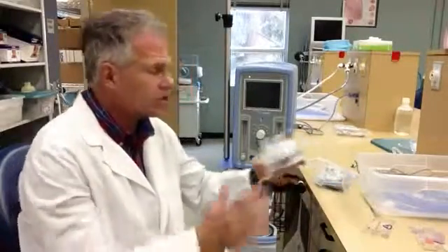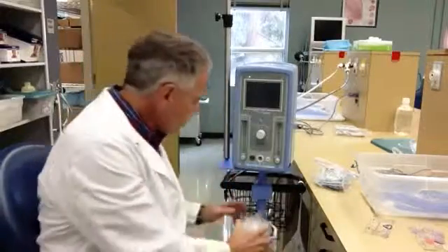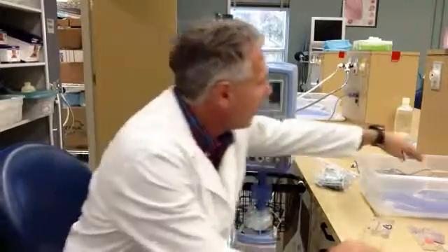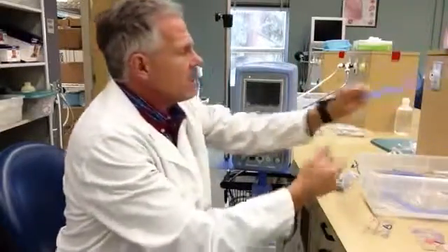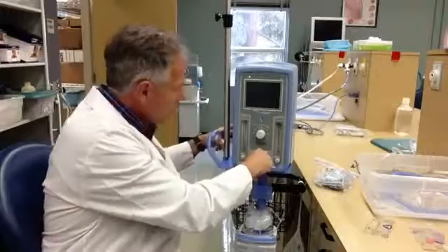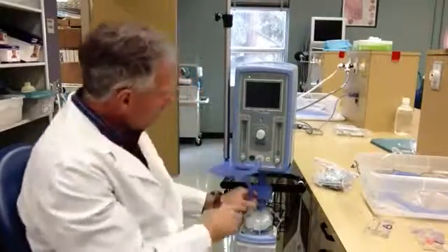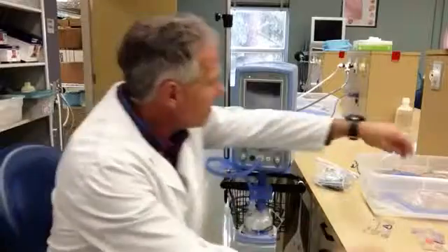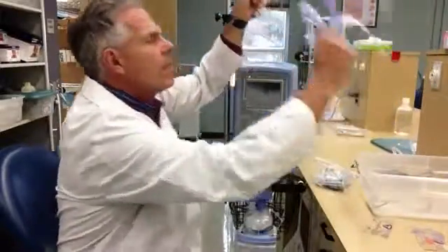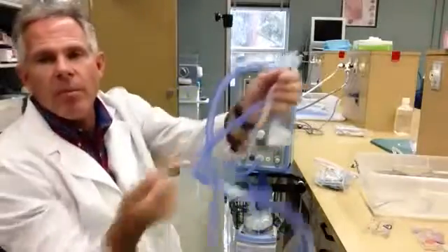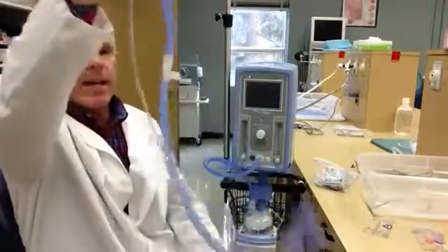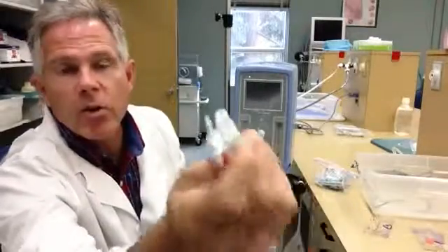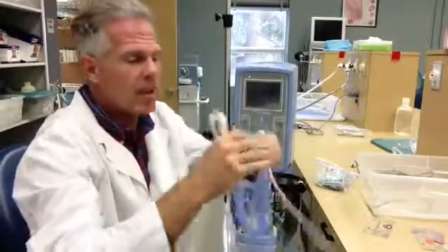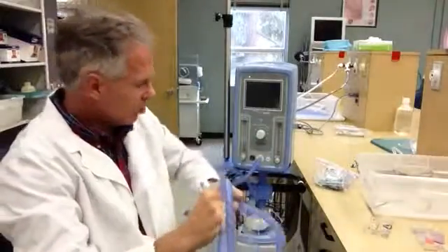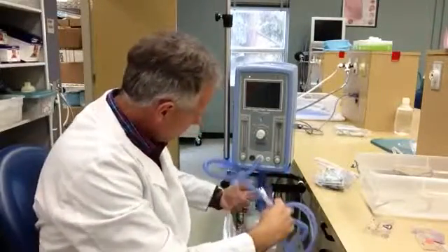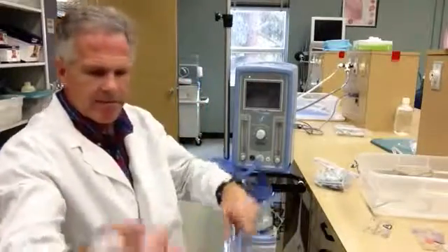Initially, before we get going, I'd like to put the circuit on first thing. It's a heated circuit, so we've got our Fisher-Paykel heated inspiratory line here. Now we need to get our gas from the ventilator, so it just hooks up right here, to the humidifier, and then from the humidifier to the patient. It's a specialized heated circuit, and it does come with special fittings on the end to hook up directly to the specialized patient connector, which I'll show you in a second. So this just hooks up right to our Fisher-Paykel, right here, just like that, okay.